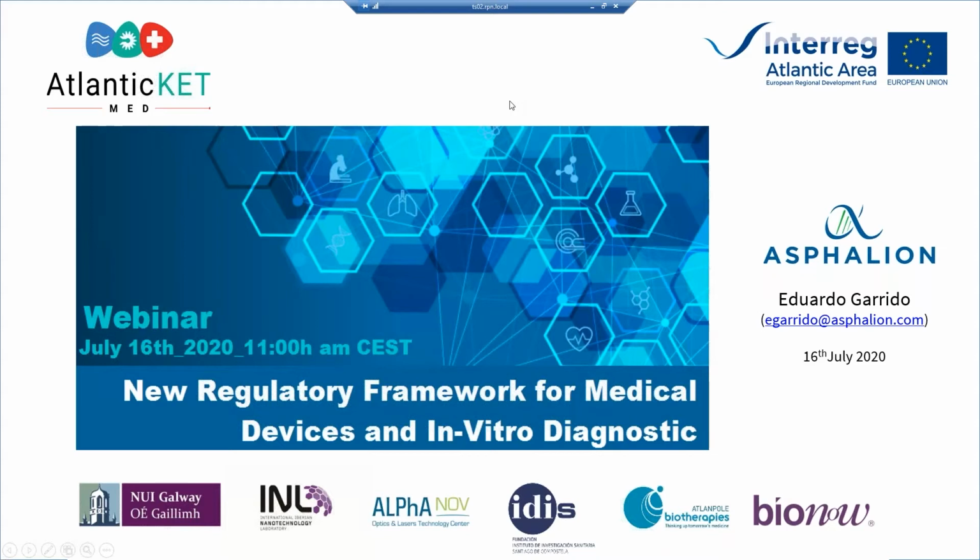Okay. So I go to the next question, which says: devices which are able to analyze in real-time samples in the hospital and not in labs, non-invasive samples such as air samples, to help in diagnostic decisions, should they be considered IVDR? If they don't come in contact with the patient and they analyze in vitro samples, yes, they are considered IVDs.